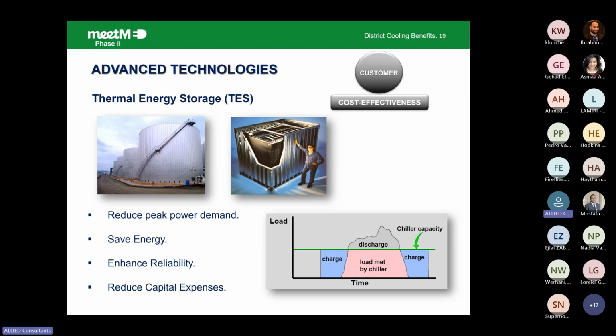In the majority of the buildings, we are utilizing thermal storage, whether chilled water or ice storage. Thermal storage, chilled storage, as we can see on the graph below, is reducing the chiller capacity by almost 20%. So instead of demanding power supply from the power plant, we are reducing the power demand by 20%, adding to this the diversified load of the district cooling plant.